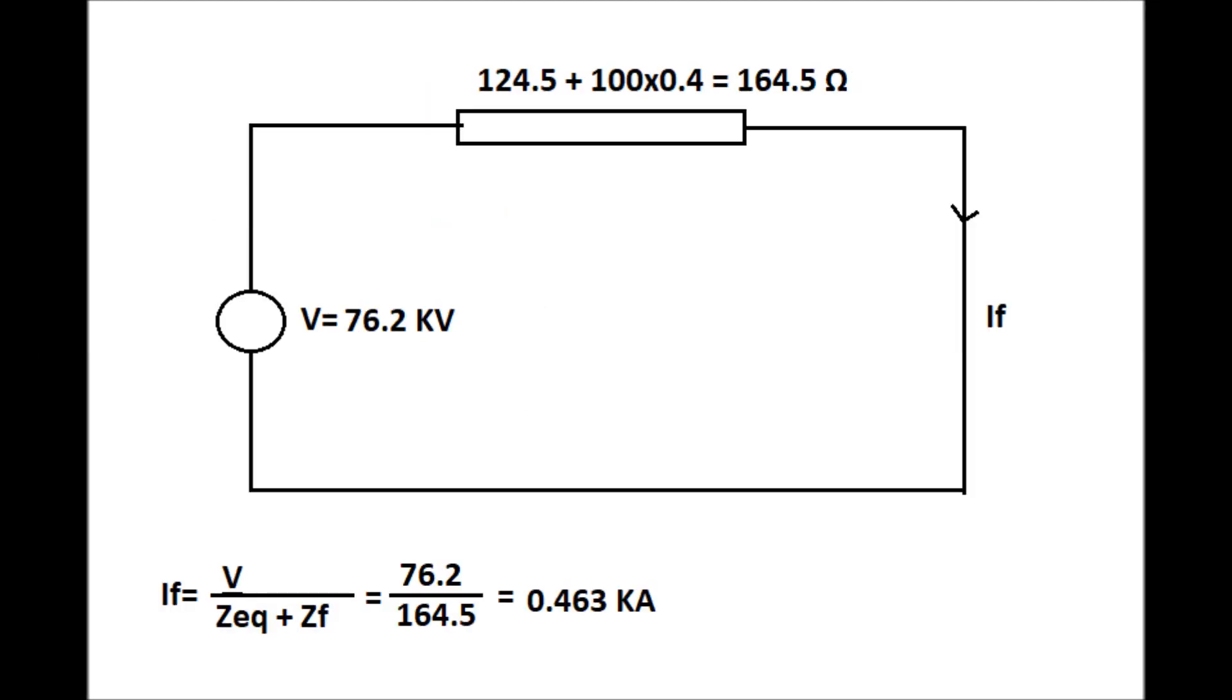The equivalent circuit for fault calculation is finally drawn in this figure. By this figure, we can now calculate the fault current for three-phase fault at point A. If will be equal to 76.2 by 164.5, that will come to 0.463 kiloampere.